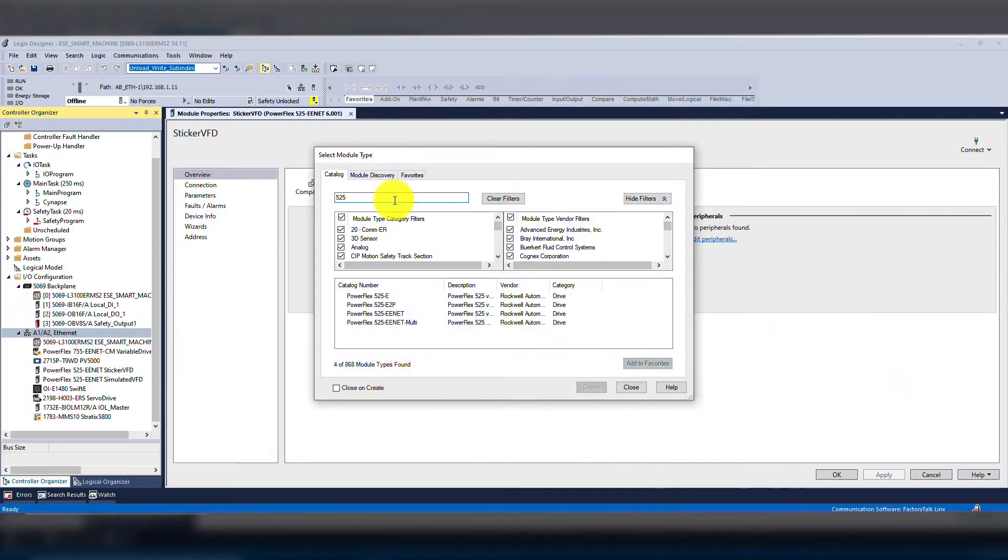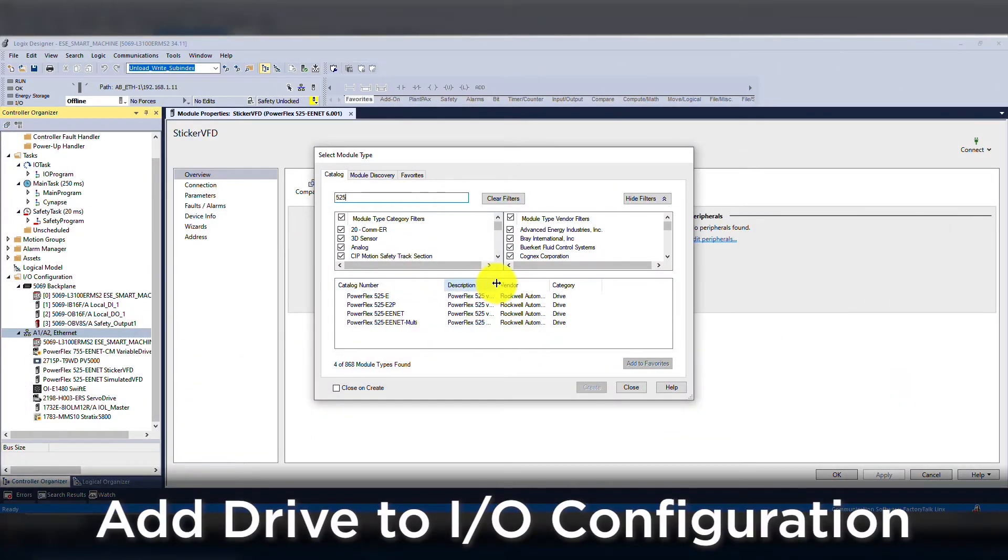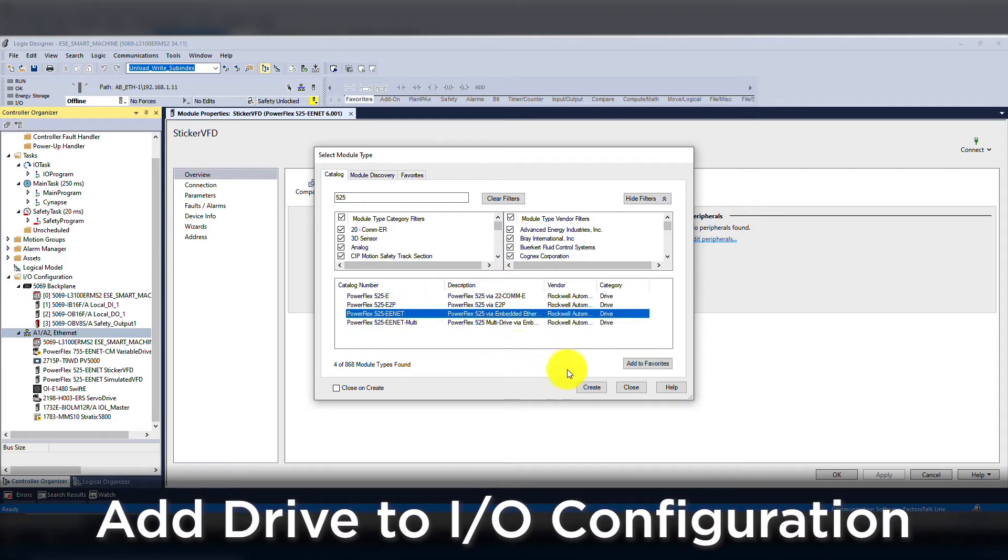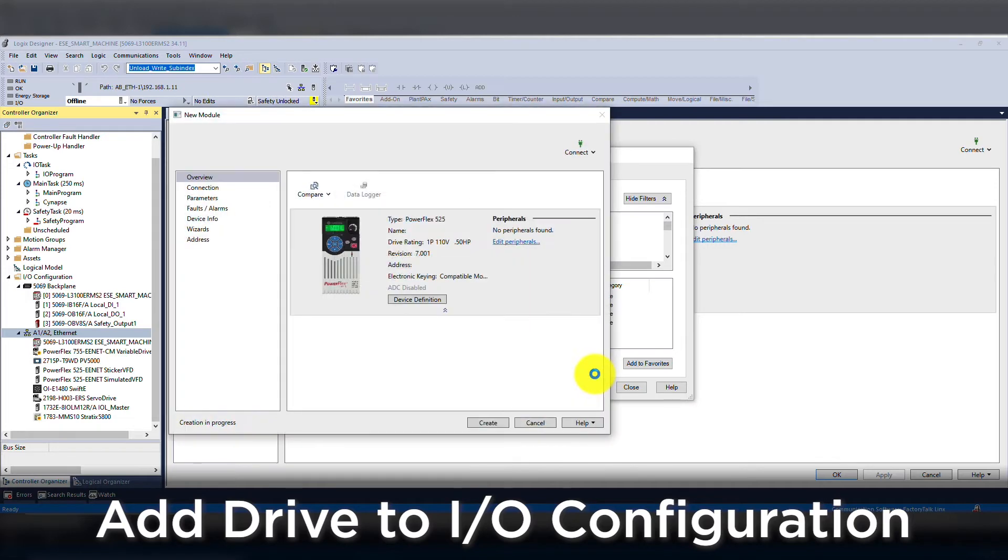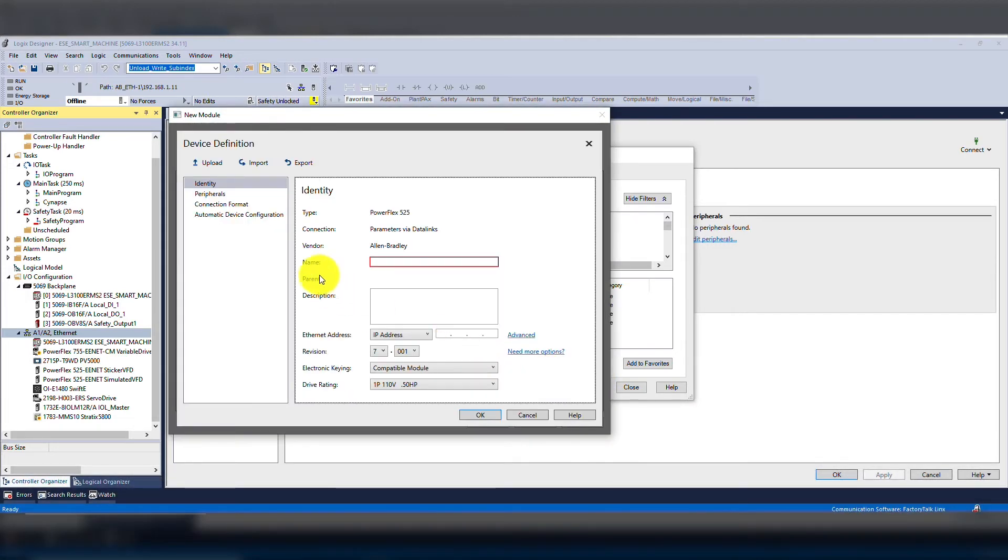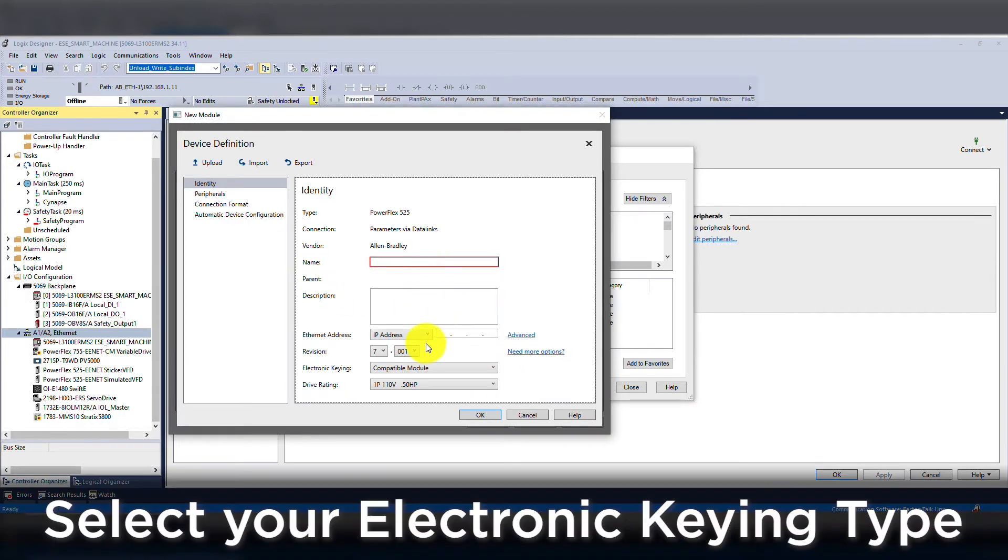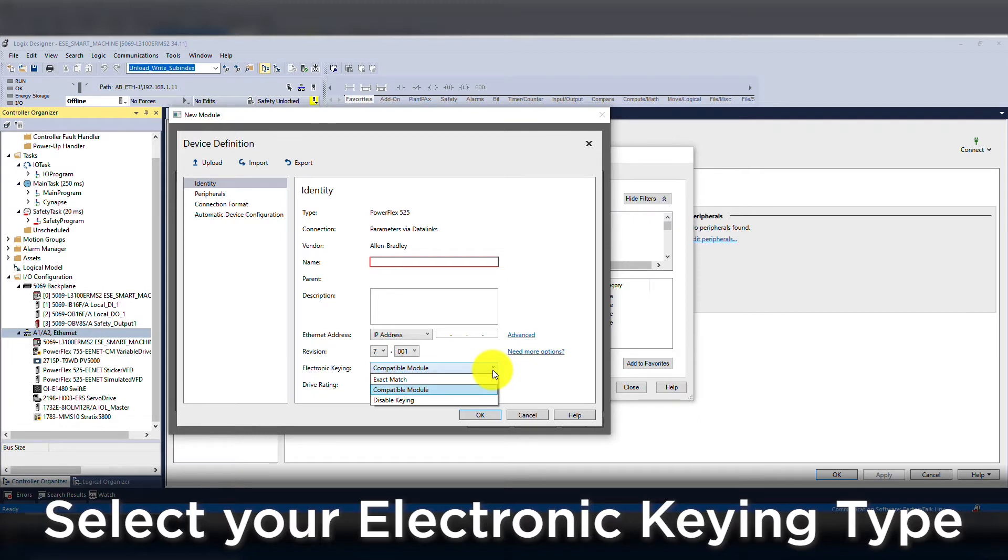So what steps are needed to configure a drive for ADC? First, we will need to add the drive to our IO configuration, which we will use default parameters. Then we will want to upload the drive parameters. In the drive module configuration, we will need to determine if we want to set up for disable, compatible module, or exact match.